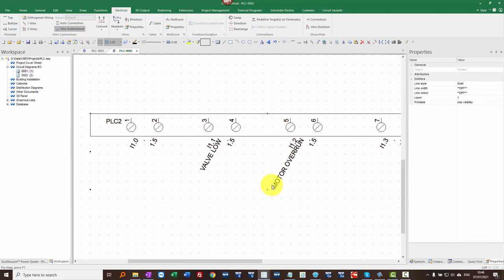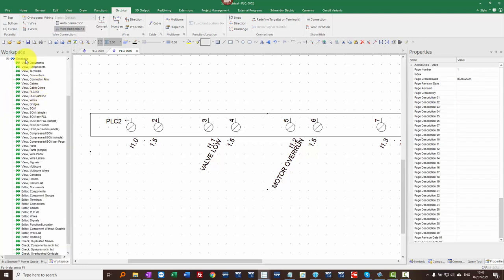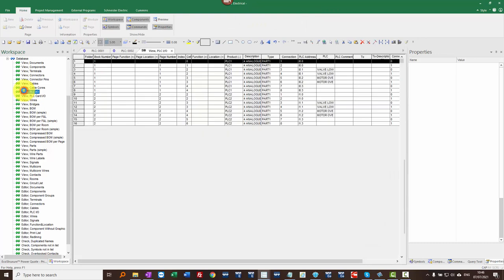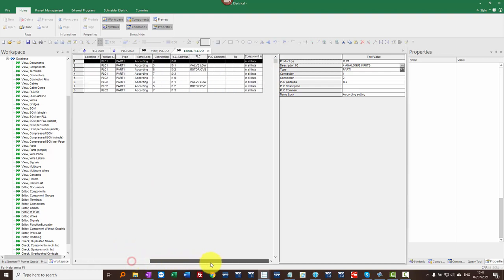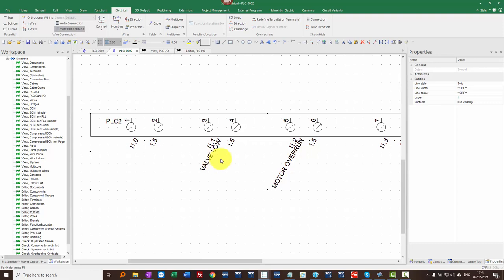With this functionality, this is the expected way of using PLCs in SEE Electrical, and it allows the full range of functions. You can import I/O data from spreadsheets at the advanced level, and you have the full range of PLC reports and information. Under Database, you can go to the I/O information where you can see and edit all of this information directly. If you create a PLC symbol in a different way, you may lose some functionality — such as the ability to number wires according to the PLC address or import from spreadsheet — so just be aware of that when creating your own symbols.